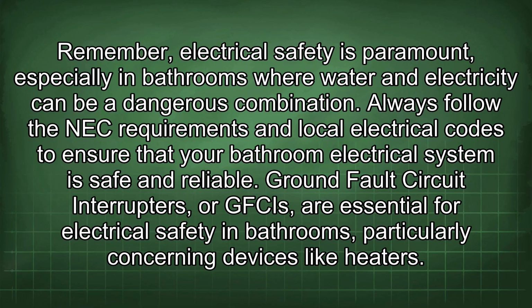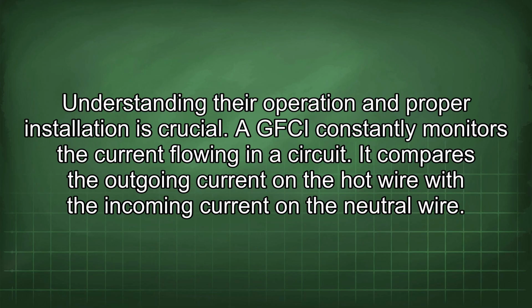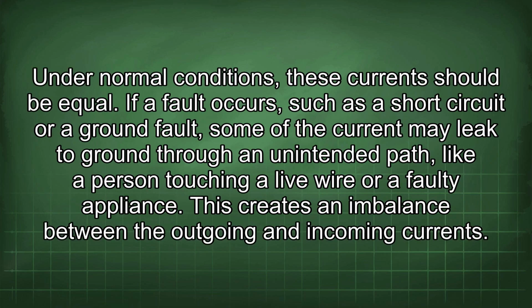Ground fault circuit interrupters, or GFCIs, are essential for electrical safety in bathrooms, particularly concerning devices like heaters. Understanding their operation and proper installation is crucial. A GFCI constantly monitors the current flowing in a circuit. It compares the outgoing current on the hot wire with the incoming current on the neutral wire. Under normal conditions, these currents should be equal. If a fault occurs, such as a short circuit or a ground fault, some of the current may leak to ground through an unintended path, like a person touching a live wire or a faulty appliance.